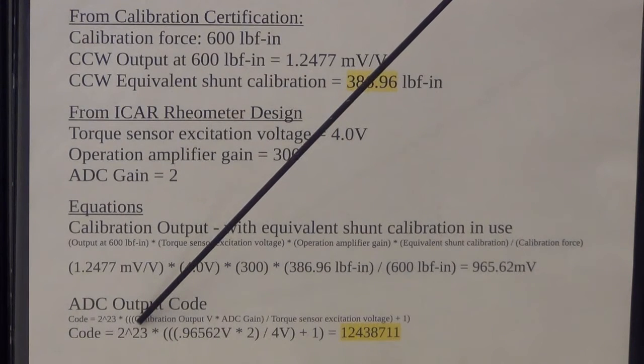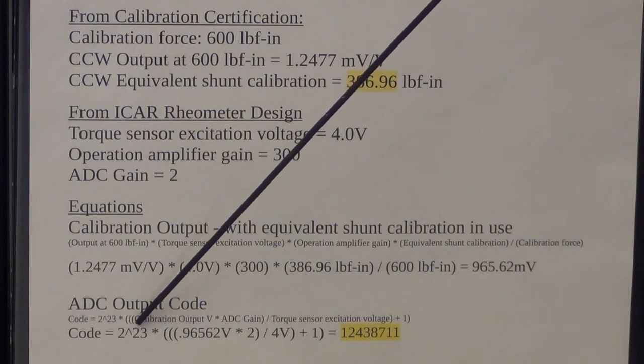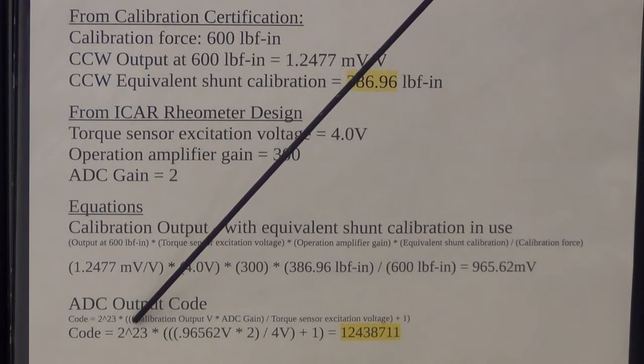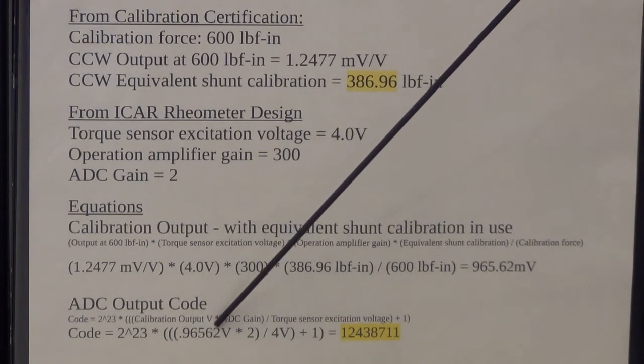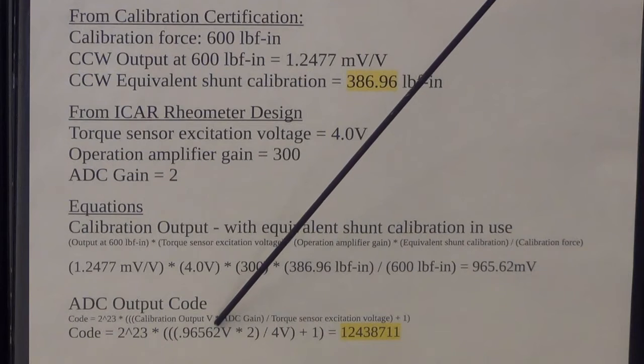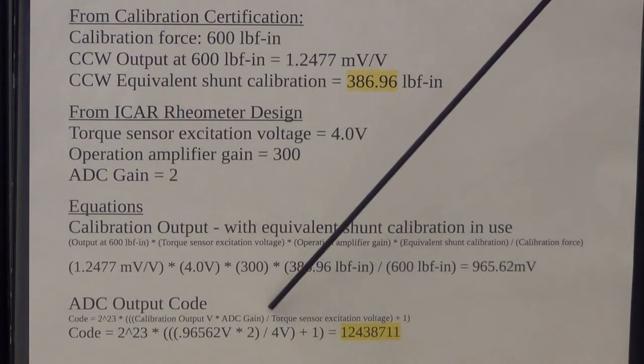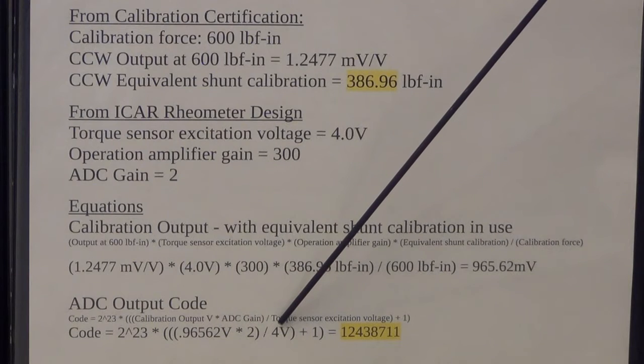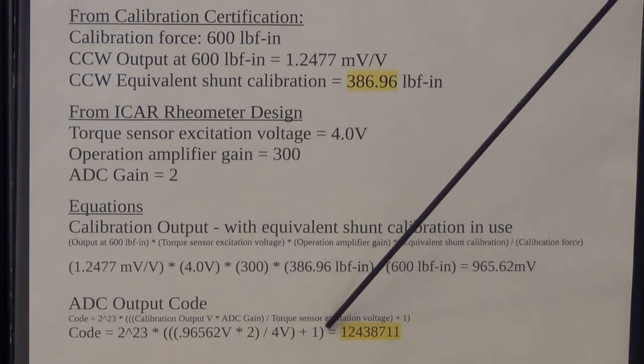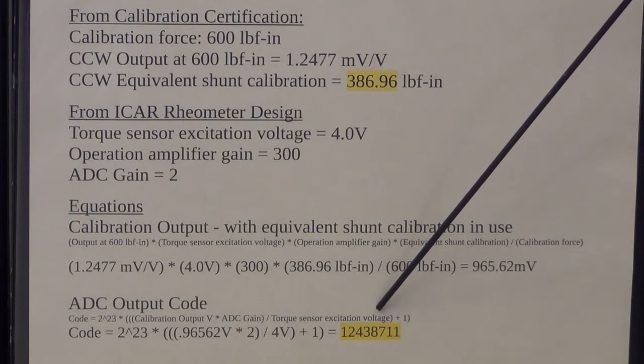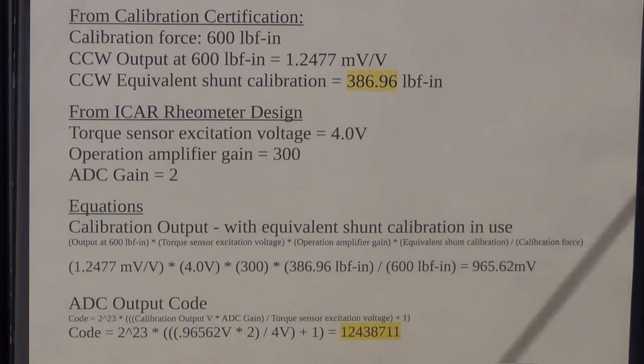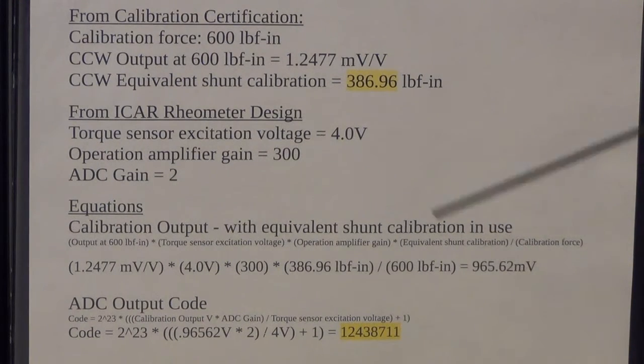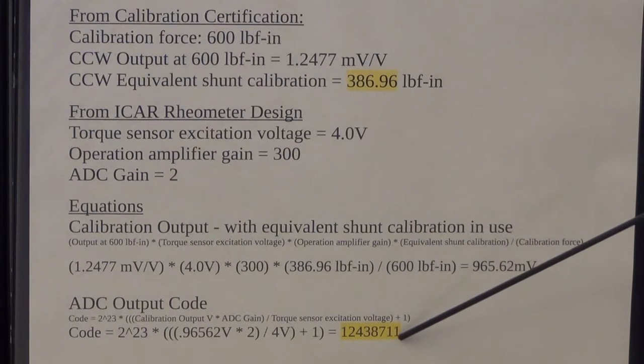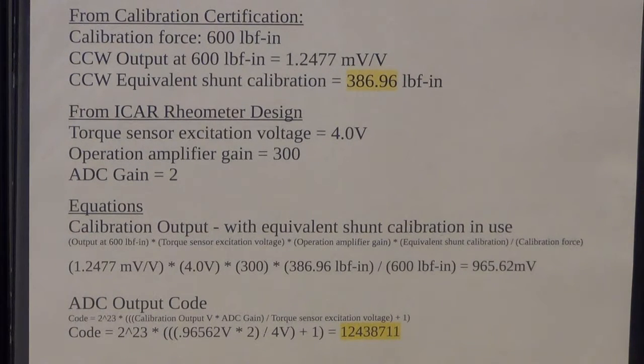This is a 24-bit analog to digital converter. We are centering the signal at half scale. Since it's 24-bit, half scale is 2 to the 23rd. Then we multiply it times the output, the anticipated output of the resistor, times 2, divided by the amount of power we're sourcing to the sensor, plus 1, gives us this magic number, 12,438,711. So there's a software tool that will put this and this value into our Rheometer, and it's calibrated.